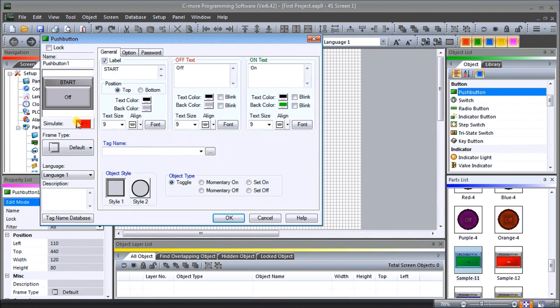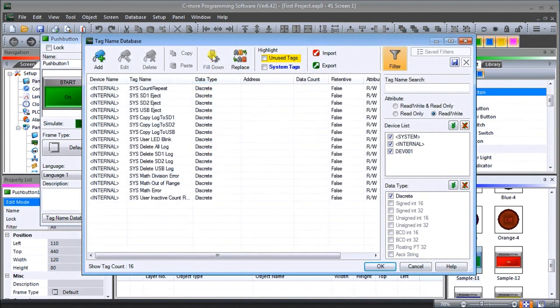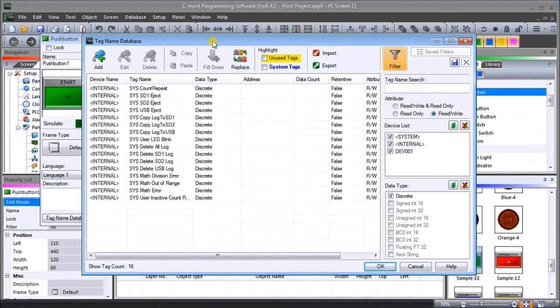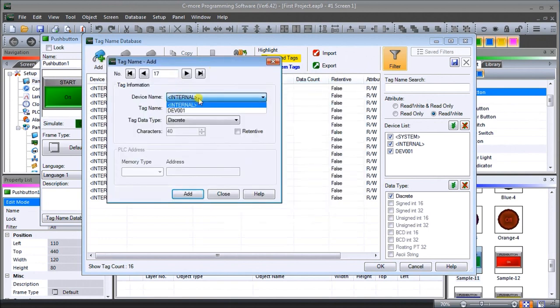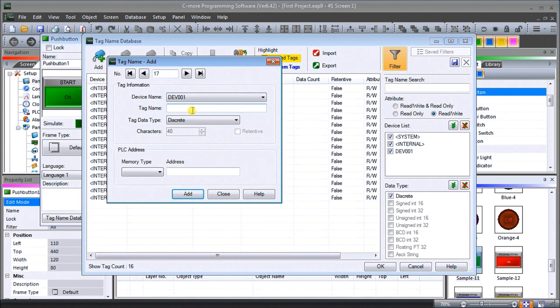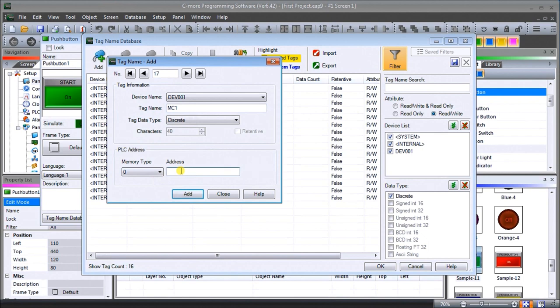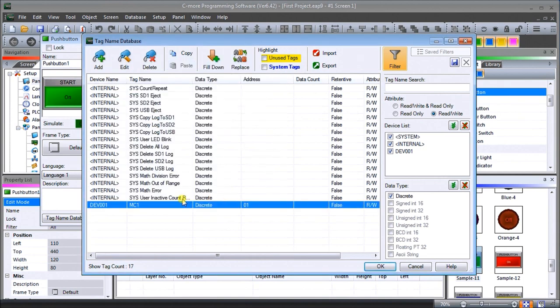We go down and we can look at our tag name. Our tag name, if we click on the four arrows here, brings up our tag database. The tag database will actually allow us to set all the internal or the communication tags that are going to be updated every time we communicate to the PLC. We're going to add a tag, and that tag will be device DEV001. We're going to call this tag MC1 and our memory address will be zero and it's going to be one. We'll just hit Add.